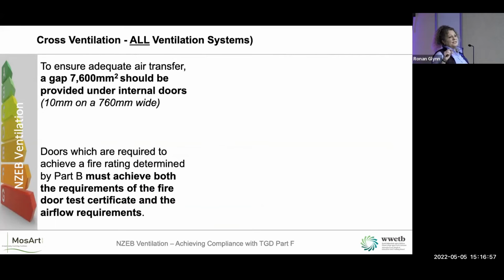Now, there was a mention of the 10 mil gap there earlier. What it states is 7,600 millimetres squared. So that's a 10 mil gap on a 760 wide door. If you have a wider door, you have less of a gap, okay? If you need to put in a mesh and seal, that will only swell up to 8.5 mil, so put a wider door in, okay? Or put a transfer grill with a mesh and seal in it either.